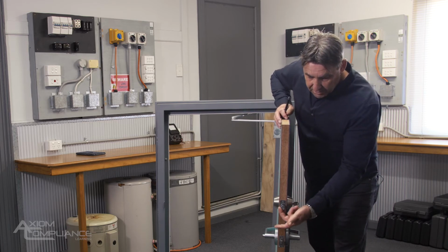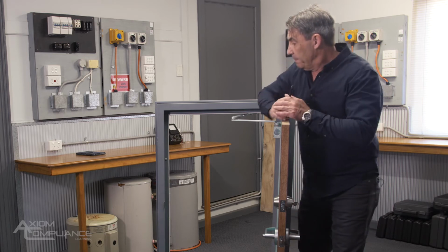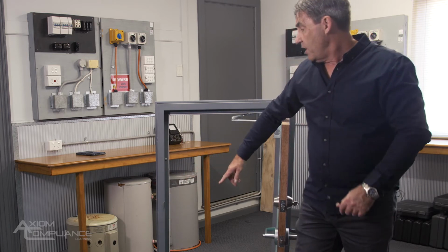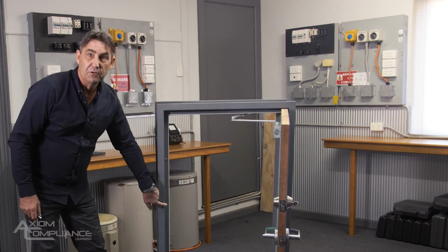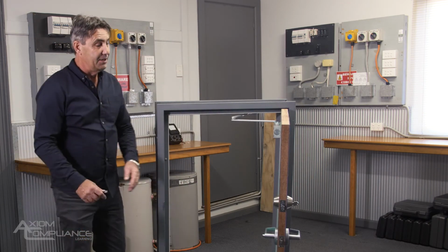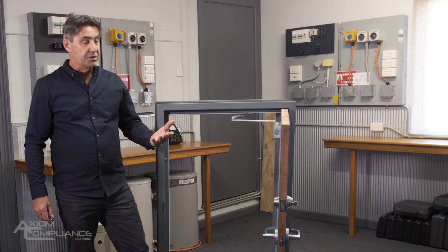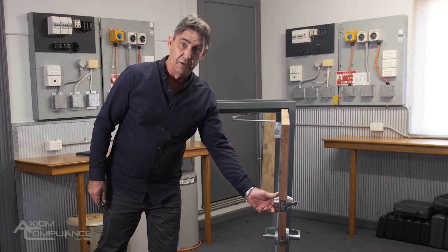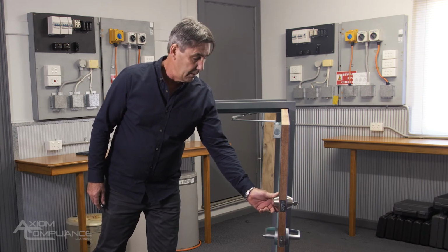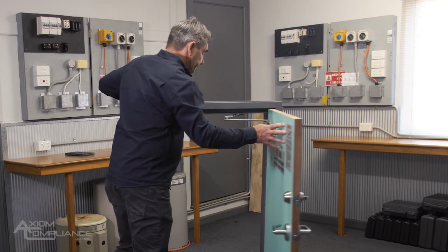And the lock set must have a beveled edge on it so that it also has a door striker which will aid the closing of the door automatically. So there are conditions on this lock set. So this door fails because somebody has changed this lock or put this lock on, and it's definitely a non-compliant lock, okay? The other hardware that I've got is on my hinges.